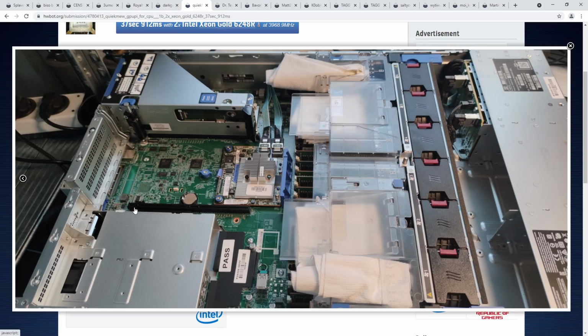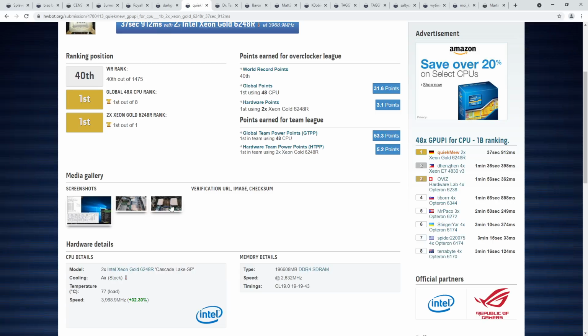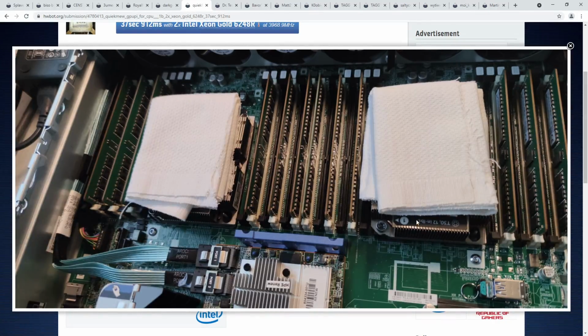Interesting, the cooling setup for servers is kind of interesting. If you're wondering what's up with those towel-type things, this is to force more air through the actual CPU fin stack, the CPU heatsinks. If you don't have those towels jammed in above them, a lot of the air would just go over the fin stack instead of through it, which doesn't do you any favors in terms of cooling. So that's what's going on there.